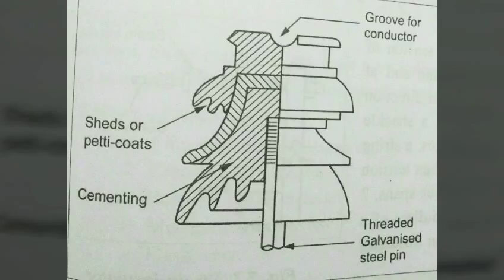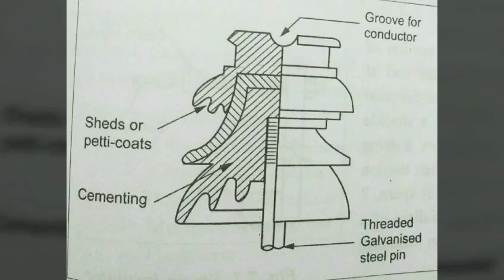These are so designed that even when the outer surface of the insulator is wet due to rain, sufficient leakage resistance is still provided by the inner dry surfaces. Pin type insulators are normally used for 11 kV, but can also be used up to 33 kV for transmission and distribution. It is not desirable to use them above 50 kV as cost becomes more.